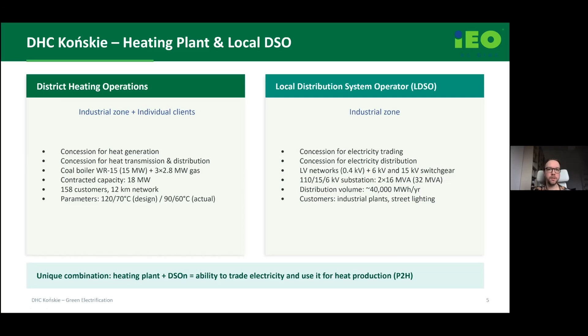We tried to size this new system with a heat pump, and our goal was to achieve more than 50% of the heat demand from the heat pump. We sized this heat pump to 3.5 megawatts thermal power, with an average COP of approximately 2.6, which is lower than the COP you would see on the residential side.